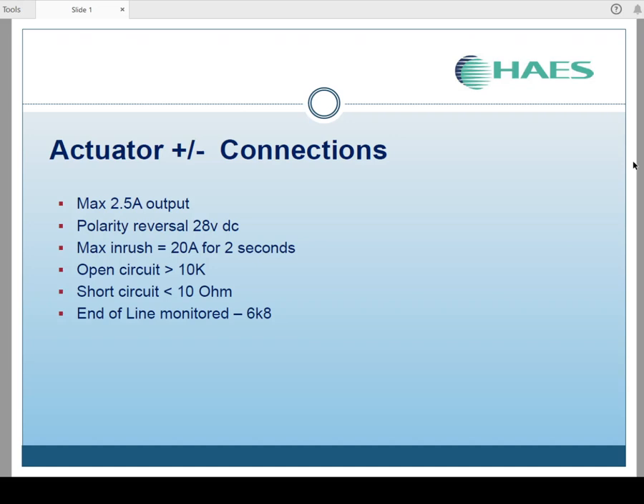And your circuit there is open circuit monitoring of 10K. So anything above 10K on that input will show up as an open circuit. Anything lower than 10 ohms will appear as a short circuit on the actuator input. Most motors will be in the middle there, so most motors will act as the end of line, so you won't require an end of line. But if you have a motor that's higher than 10K, it's still usable. You fit a standard 6K8 monitoring resistor on the motor itself. It's fairly rare. Most motors will monitor quite accurately.